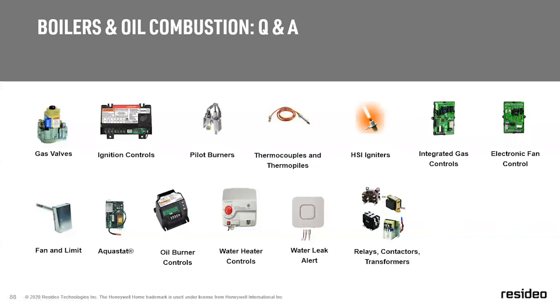That is not adjustable. It either drops out after flame is established, or you can keep it on interrupted throughout that burner cycle. Hope that answers that one. Yeah, that's correct, Rick. It can be chosen as an interrupted or the intermittent control, and it's your choice. It will just point out if it does not prove, it will document that in the error area.